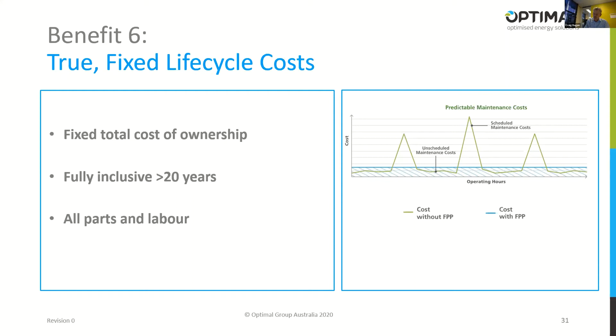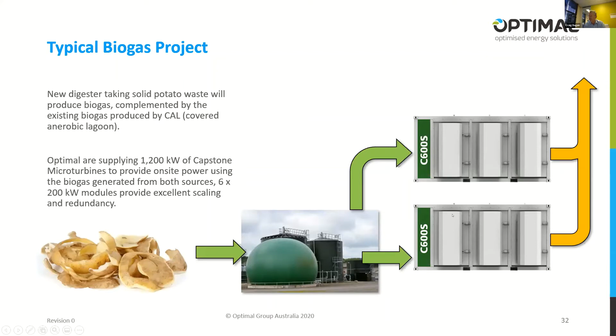So this is a project we're doing at the moment for McCain's in Ballarat. They take in 600 tonnes a day of potatoes, and they get 200 tonnes a day of waste. Currently it's going to anaerobic lagoons, but it will soon go into an anaerobic digester. That produces enough methane for us to run 2 600 kilowatt turbines, which is in fact six 200 kilowatt turbines, which is 1.2 megs.